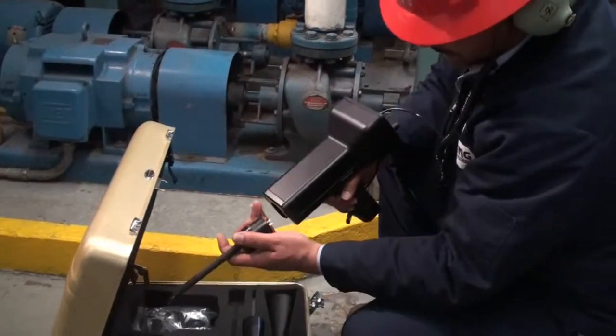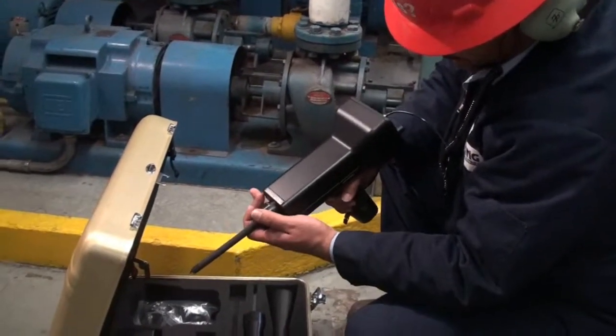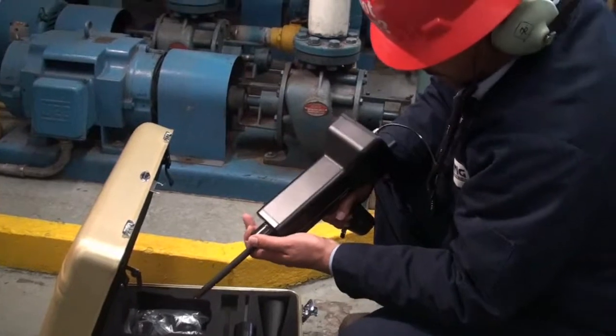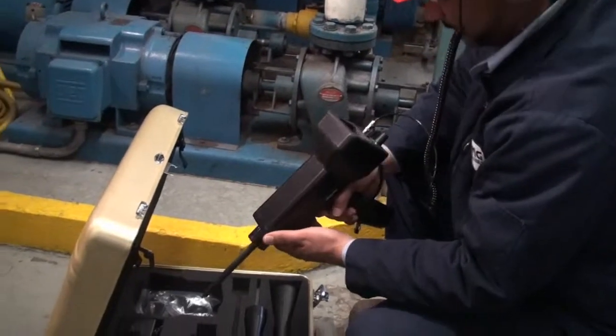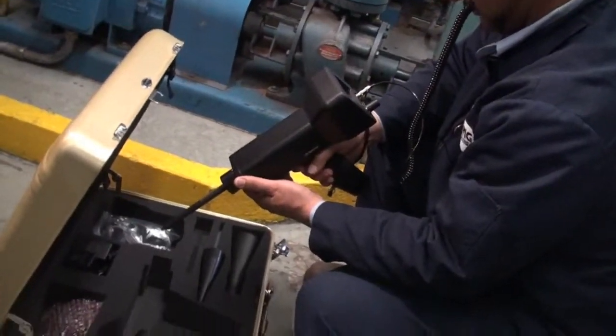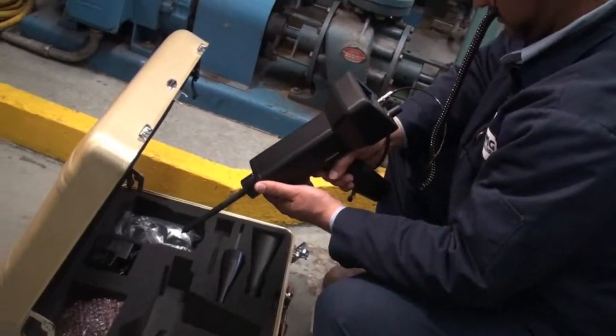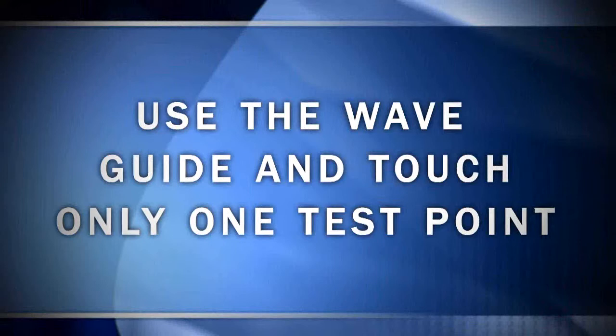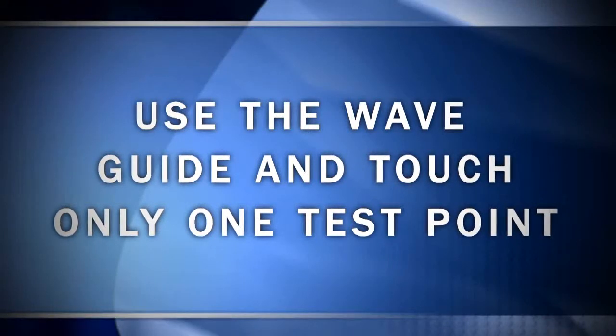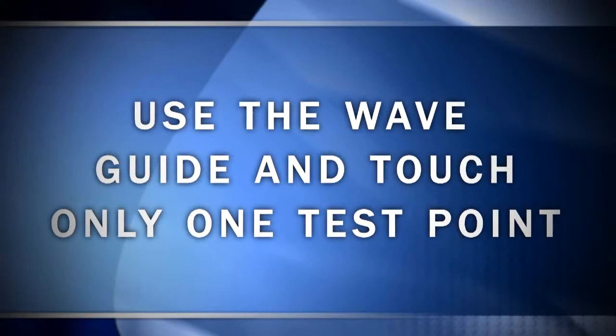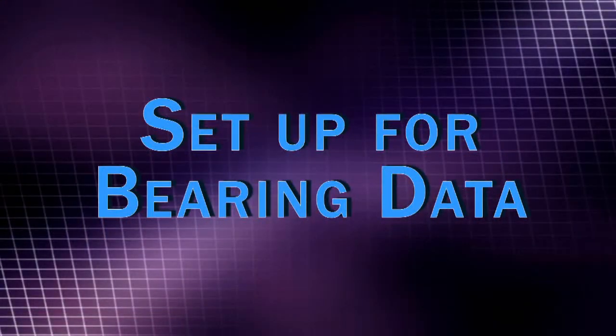This module acts as a waveguide to help us hear the translated ultrasound when we touch the bearing housing. We only need one test point when using ultrasound to get effective, accurate results. Now let's set up for testing and collecting bearing data.